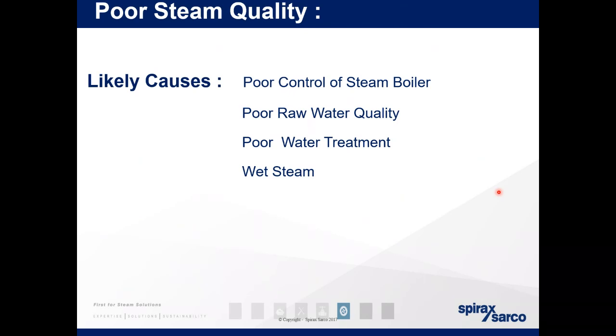Poor raw water quality. So if you are not removing the particulates in the water, such as high salt or any other scale that's in the raw water, any other contaminant that's in there, that then carries over into your boiler, which could potentially carry over into your steam system. And poor water treatment, as it says. So a lot of times we'll use these epoxy tanks, the resin tanks, to add salt to remove particulates. If you're not treating your water properly, again, it makes its way to the boiler. Then it makes its way to the steam system.